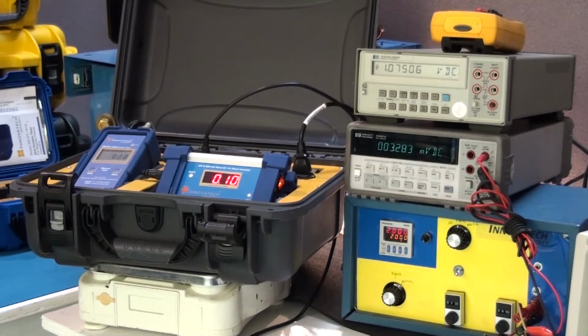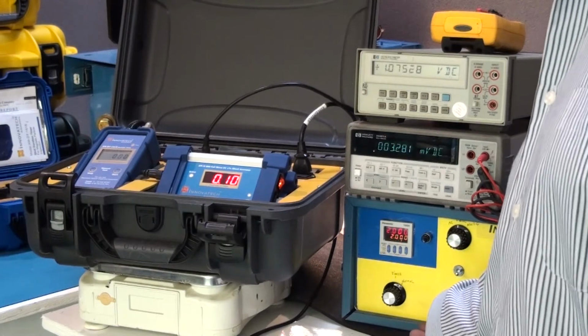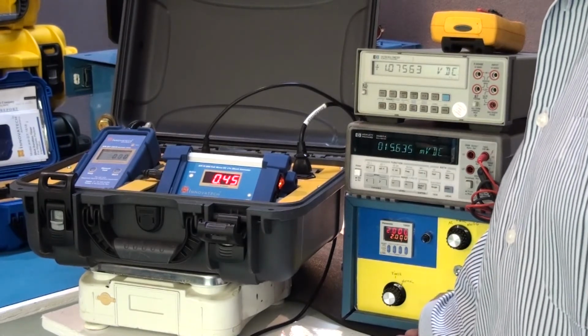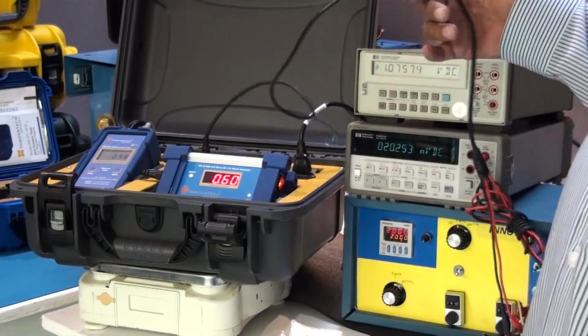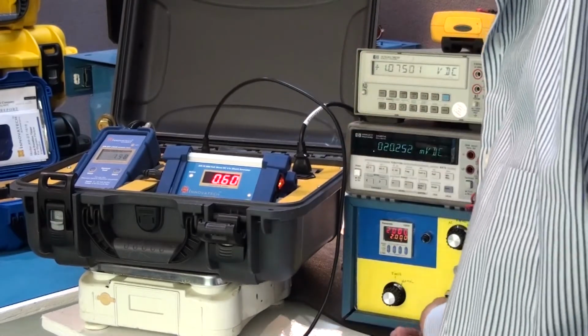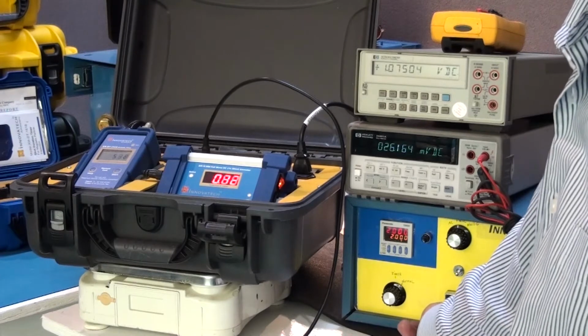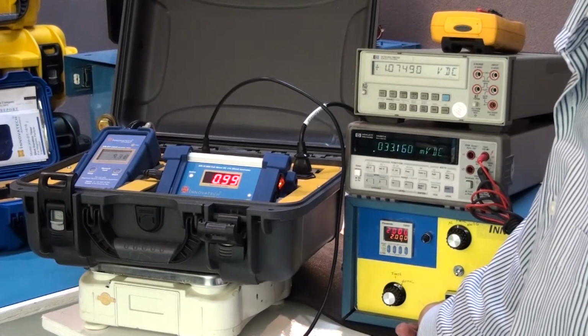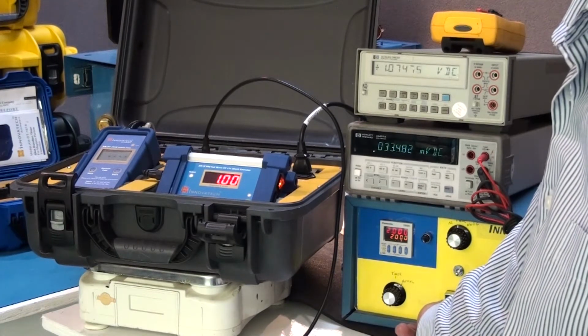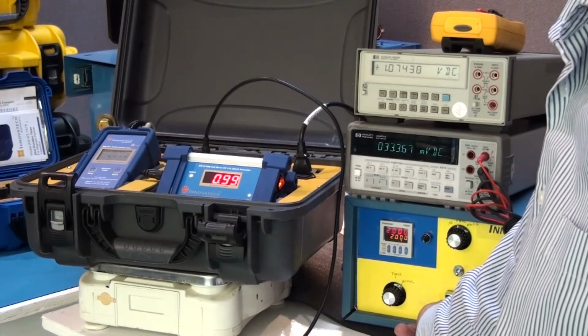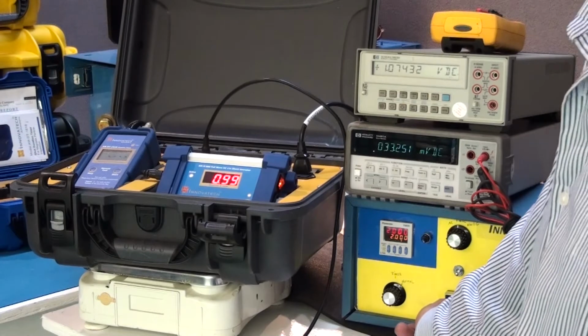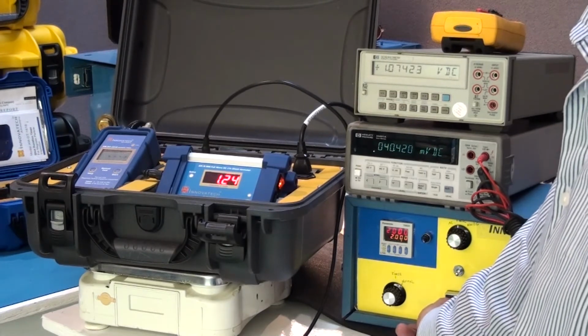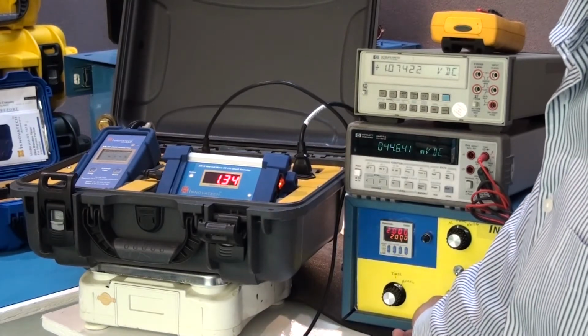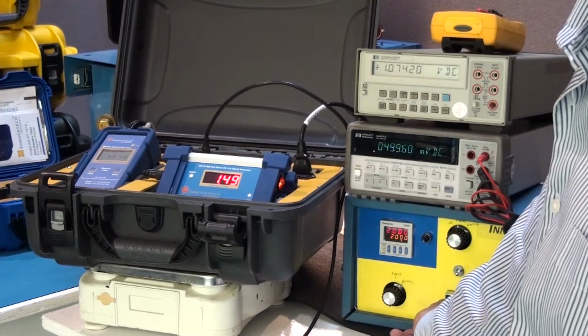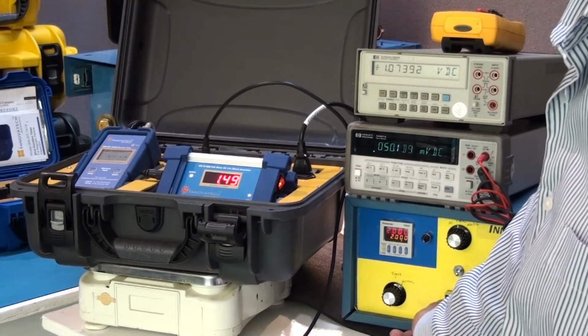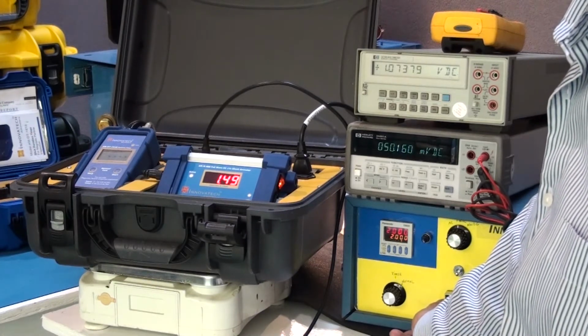Now we'll run this up to 33.3 millivolt input. And here's our cable. And you see that we are right about 99. So we're at 990 amperes. So we can run this up to 50 millivolts, and this should be at 1500. The meter should read 1500. Okay, 1499, it's in spec.